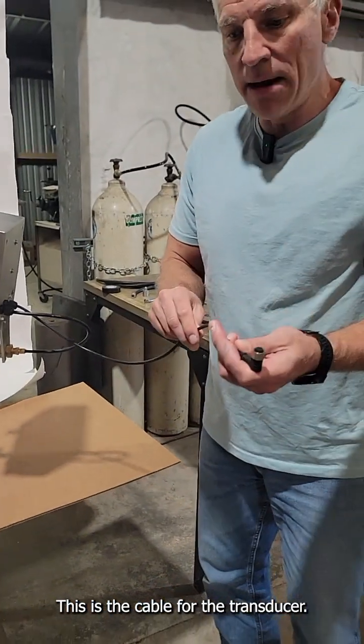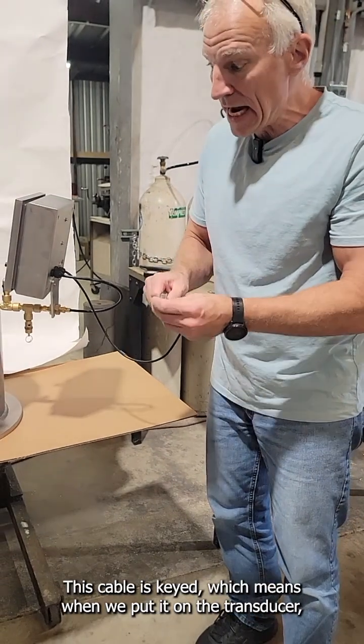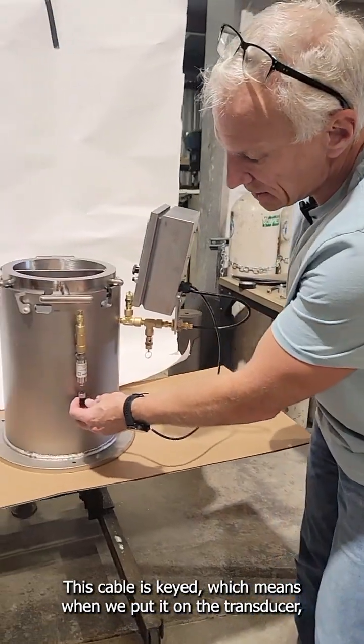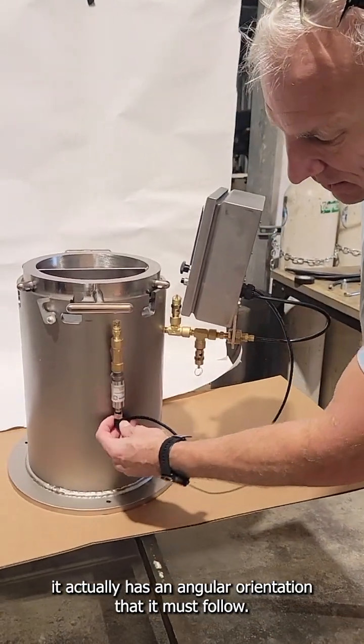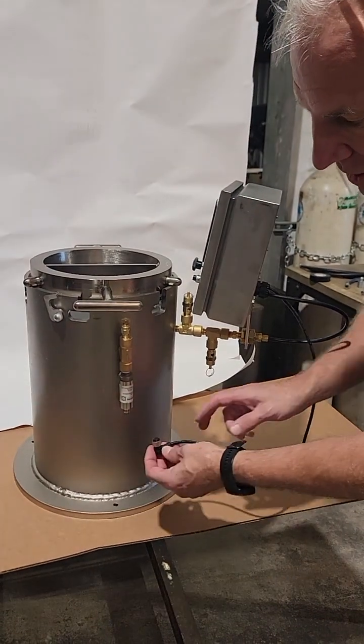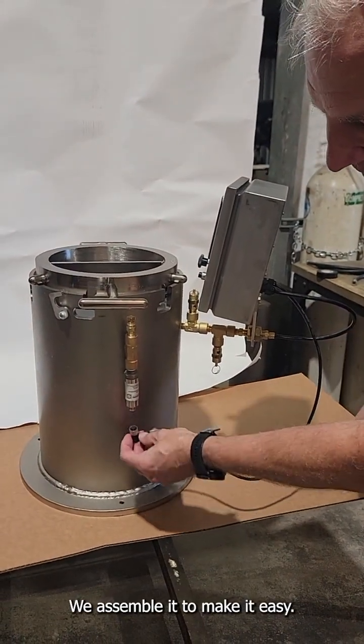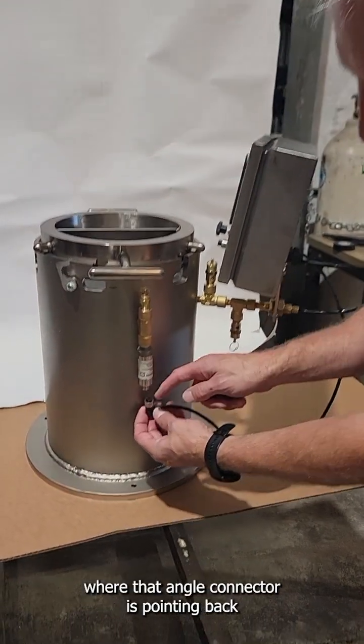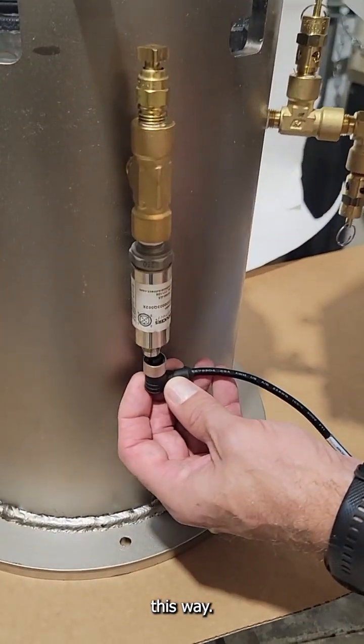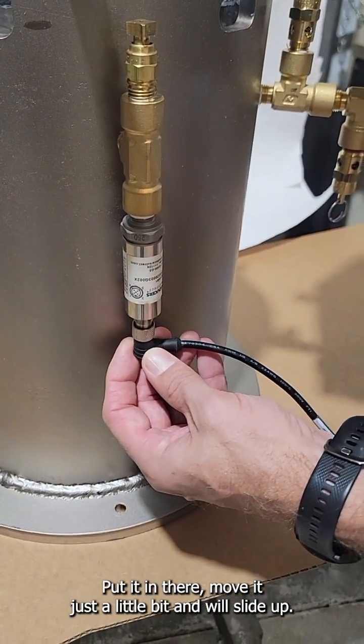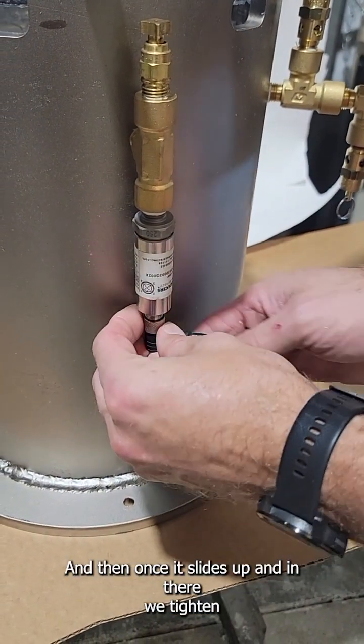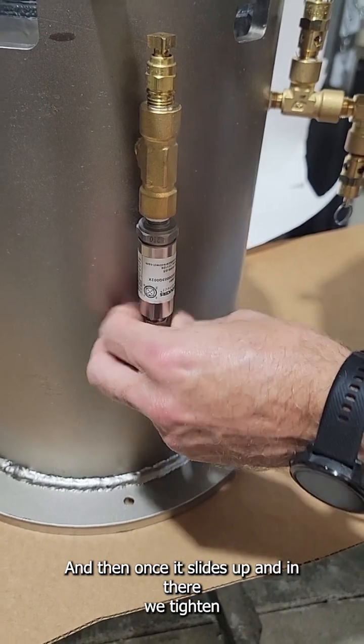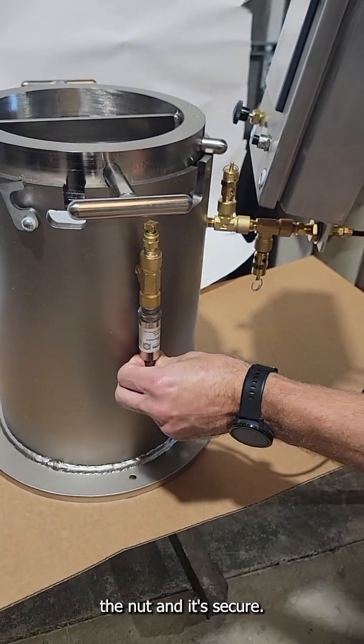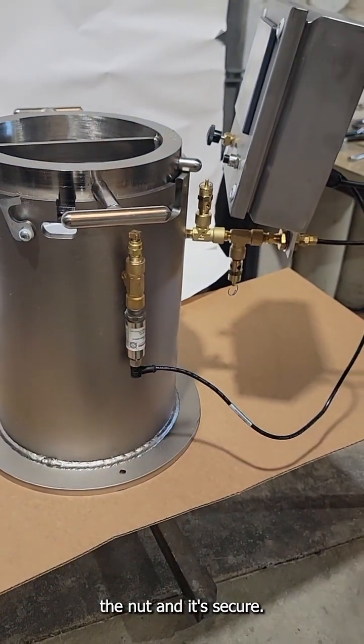This is the cable for the transducer. This cable is keyed, which means when you put it on the transducer, it has an angular orientation that it must follow. We assemble it to make it easy so you can see the orientation where the angle connector is pointing back this way. Put it in there, move it just a little bit, and it'll slide up. And then once it slides up and in there, we tighten the nut, and it's secure.